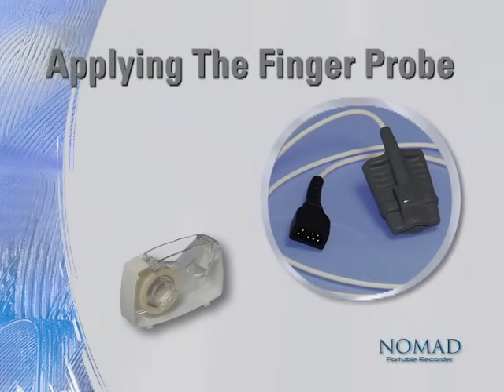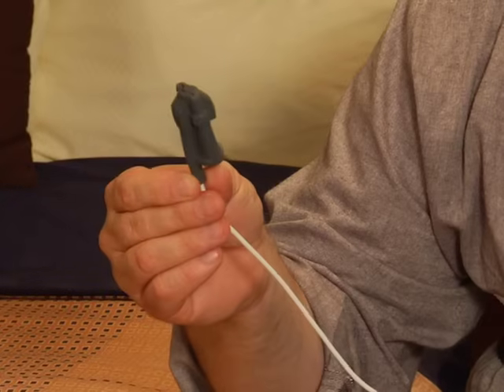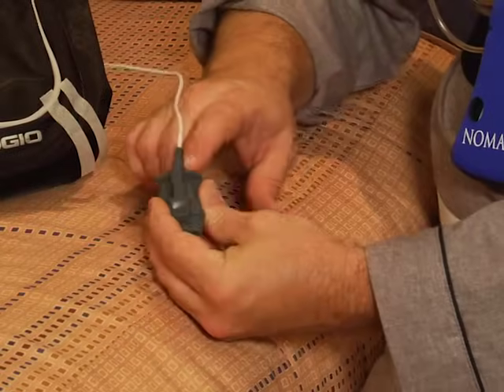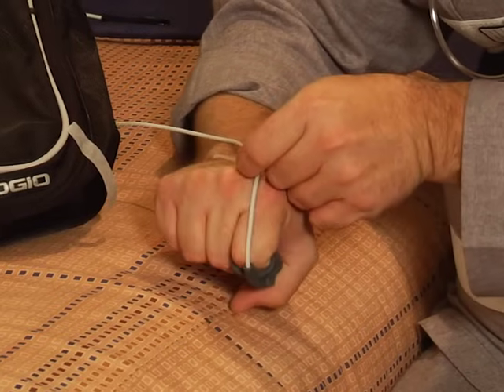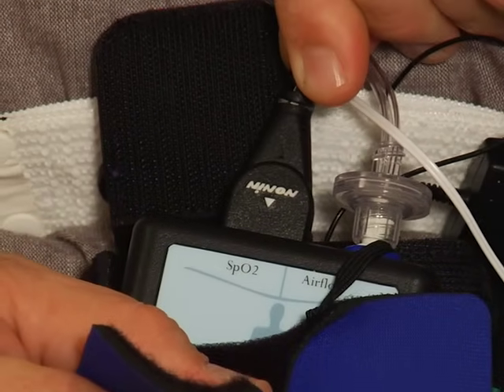Applying the finger probe is the last step of our setup. Ensure that all jewelry and nail polish have been removed before you do this final step. Find the sensor that has a rubber tip in which you can insert your finger. If you are right-handed, you'll put your left index finger into the rubber tip. If you're left-handed, you'll use your right finger. Insert your finger — providing that you've placed your finger correctly, the cable will run along the back of your hand. Next, make a fist and tape the cable to the back of your hand using the tape you prepared earlier. Apply another strip of tape to your forearm so that the cable is securely in place. Finally, just before you're about to climb into bed, plug the finger probe connector gently but firmly into the connector labeled SPO2 at the top of the Nomad.